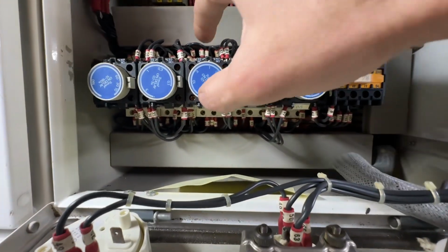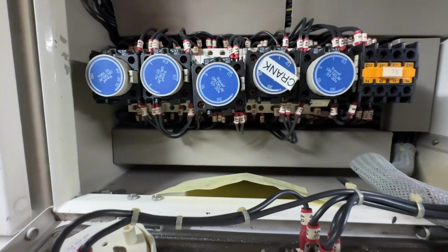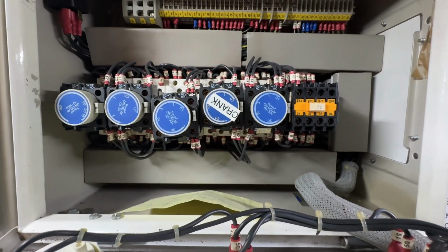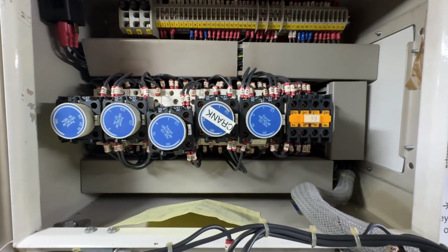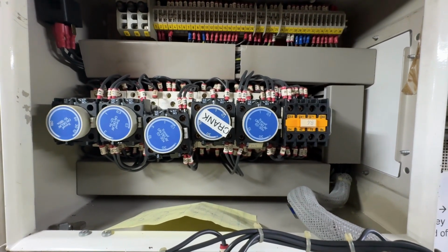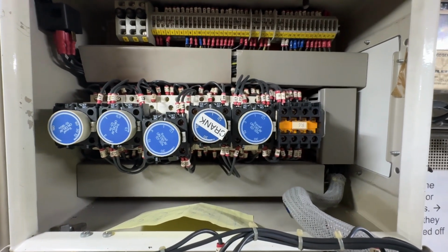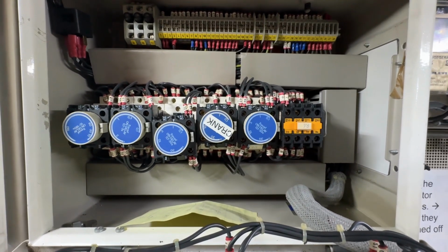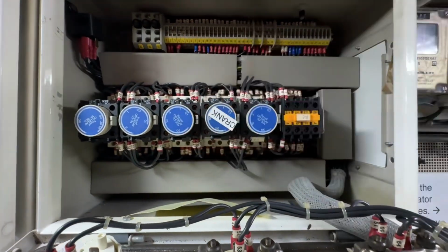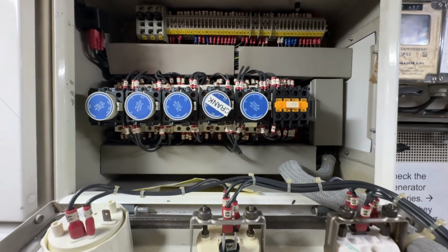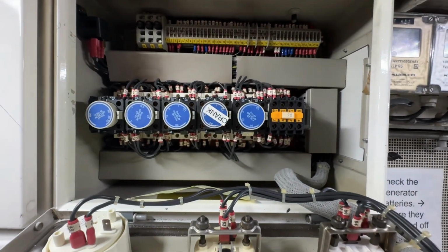Now, for example, if I were to remove one of these delay timers so that something in the sequence didn't actually complete, and then I try to start it, it doesn't start because something went wrong in the sequence, and eventually it will alarm out. Come on, let's see. Oh, there we go. So I hit the stop button, reset that alarm. So that's what the relays are doing for this timer, for this start sequence. And these are all just delay modules on top of these contactors.